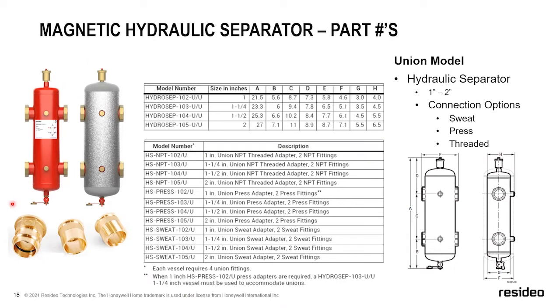The reason we're doing that is some contractors like to do iron pipe off of the boiler. So we can do threaded connections here for the iron pipe hookup. And then maybe you want to do press on this side, or maybe you want to sweat on this side. So when you buy our HydroSeps, you need to make sure you buy 2 packs of fittings. The reason is if you're doing all sweat, you can do 4 sweat connections, but you need to buy them in 2 packs of 2.